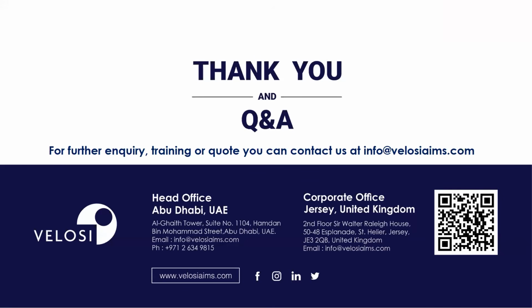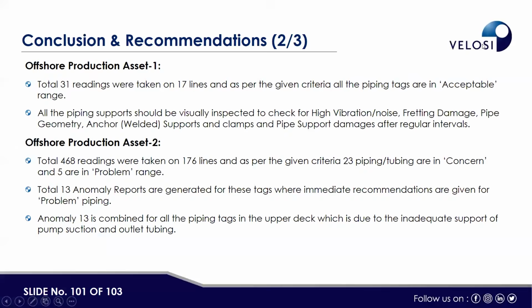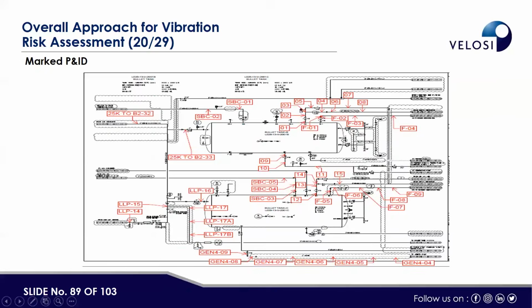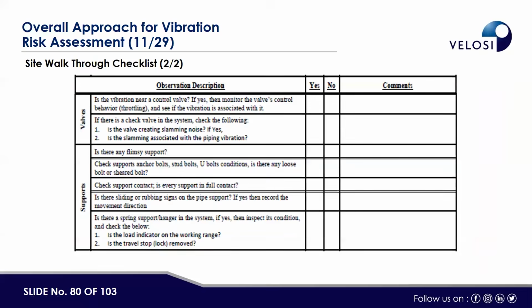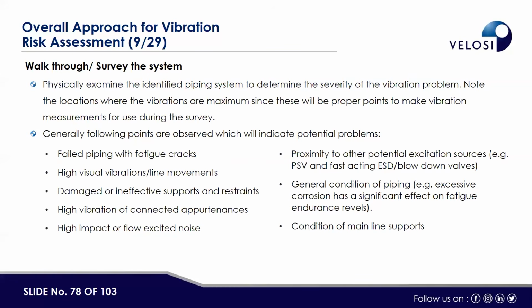Hello, Mr. Rao. My question is, what are the vulnerable locations which can lead to vibrations, for selecting the vibration monitoring locations? As you have said, the control valve upstream and downstream loops with the reducer and the line with small bore connections. So are there any other vulnerable locations for selecting the vibration monitoring locations? Can you tell us in a few points that you can share?